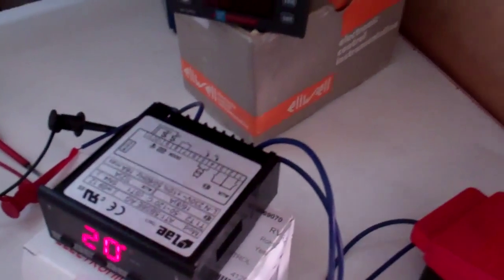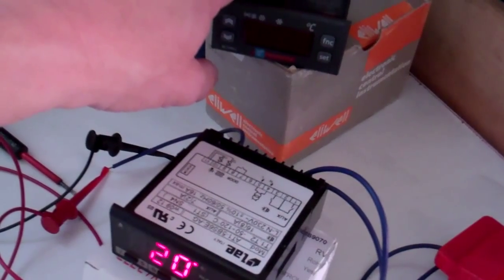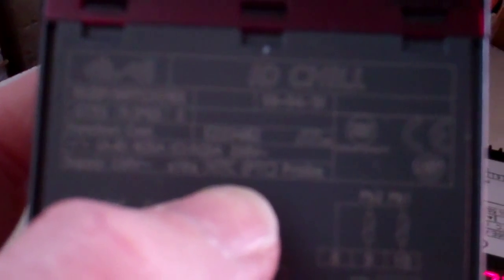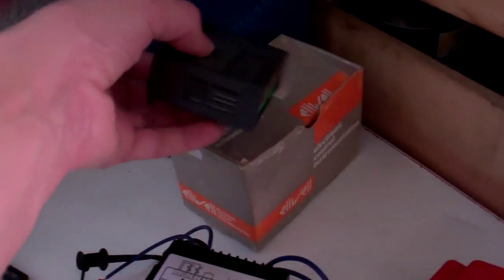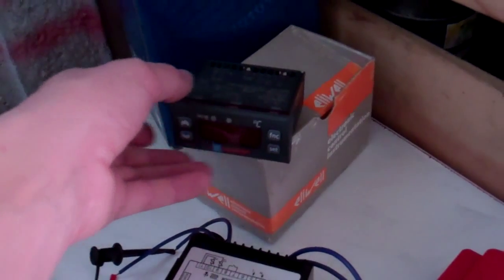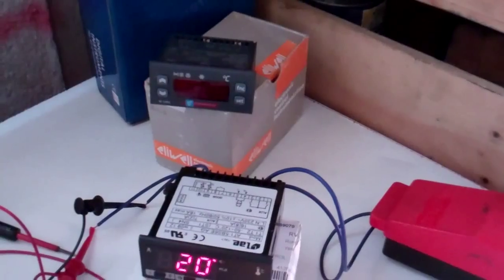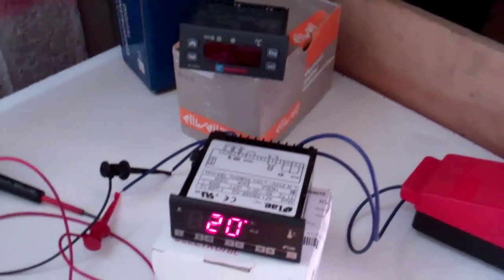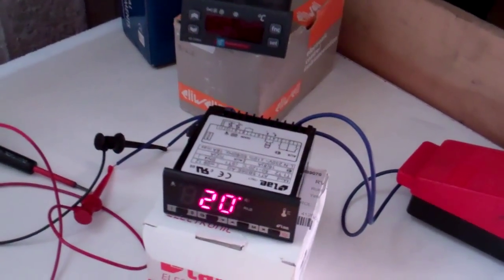But what they do or have is different types of probes like this one could have NTC or PTC, that's default to NTC probes, which is negative temperature coefficient, which means the resistance goes up, the temperature goes down. But the positive one is the resistance goes up, the temperature goes up.